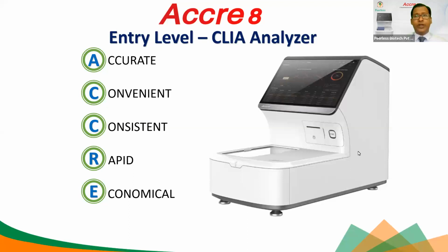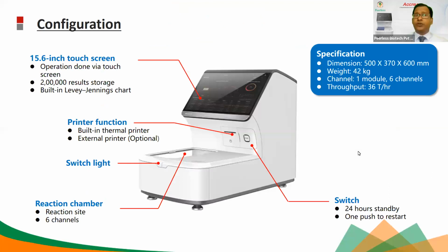Now going next, I'd like to show you different parts of the machine. This instrument has a 15.6-inch touchscreen, which is very appealing. It's quite a big touchscreen in front, and the full operation can be done by touchscreen itself. You can save 2 lakh results inside the instrument, and it has a built-in Levey-Jennings chart for quality control management. And we have a built-in printer, which will give you the printout. If the customer wants a smaller printout, they can get it. If they want a bigger printout on their letterhead, we can connect a printer to the machine and take a printout through LAN. Multiple options are available, which your technical team can do.